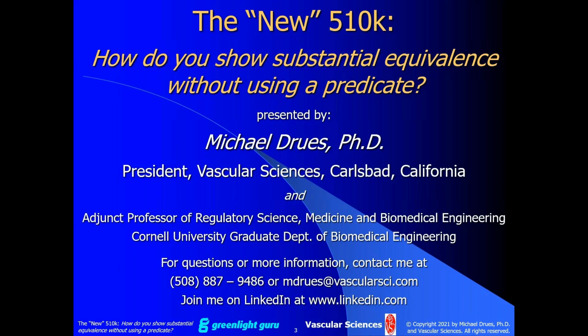What that means is you do not have to submit a 510K or a de novo or a PMA or anything else. You are still an FDA regulated medical device. You still have to be FDA registered. You still have to have a quality management system. You still have to have design controls, all that kind of stuff. But there's no formal review of your device by the agency in the form of a 510K or something else.